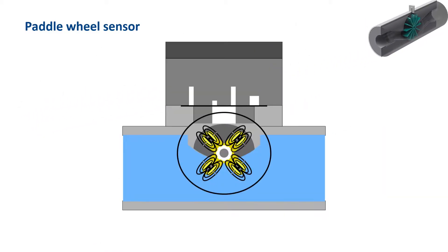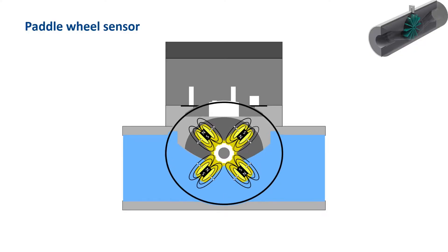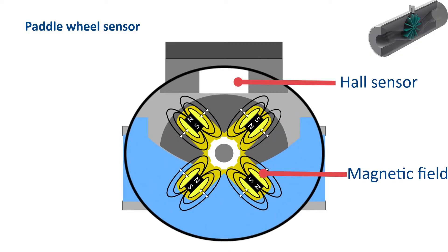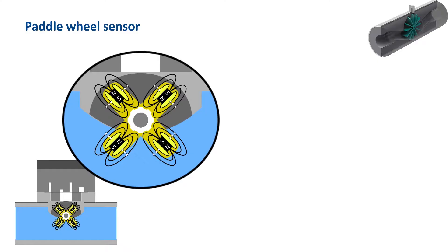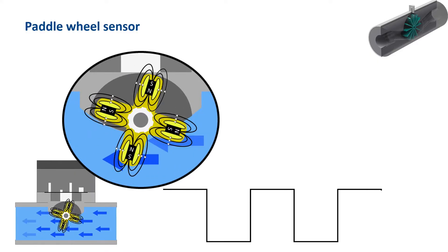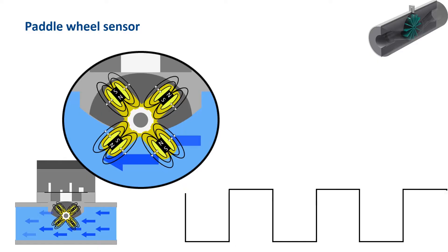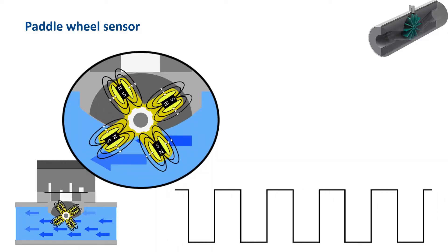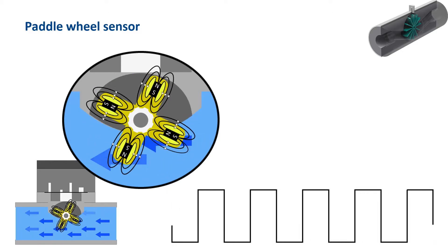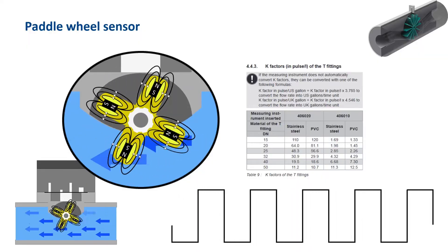In the case of the paddle wheel sensor, the permanent magnets embedded in the blades generate a magnetic field, which is detected by a Hall sensor and output as a square wave signal. The liquid flowing past drives the wheel. If the flow velocity is slower, a lower frequency is output; if faster, a higher frequency is output. The frequency of rotation is therefore the direct measure of the flow velocity. Since the output pulse frequency is proportional to the flow velocity, the field device can calculate the flow rate via the k-factor.